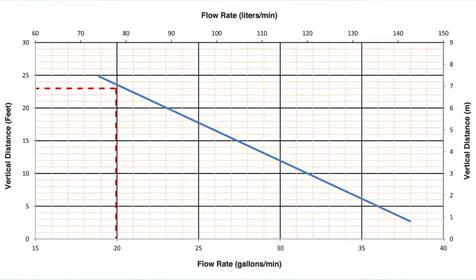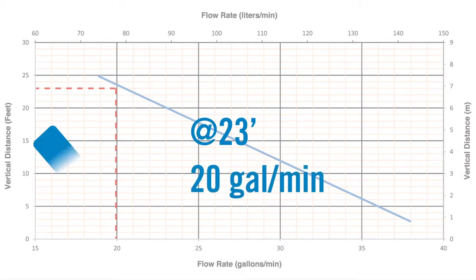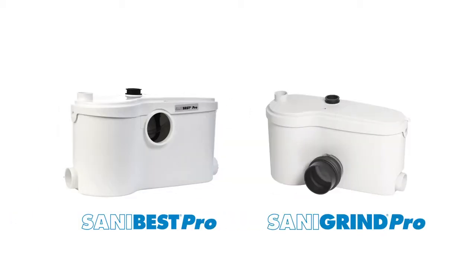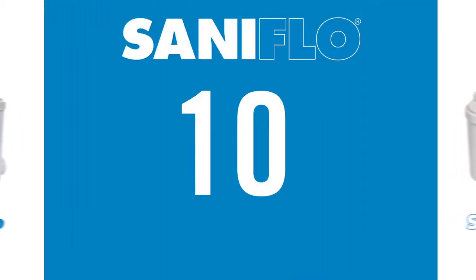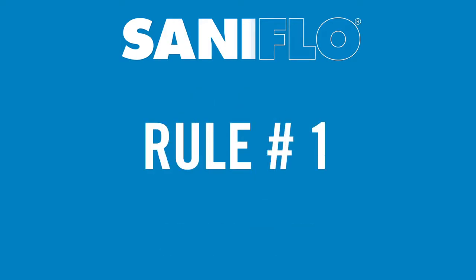By reviewing the pump curve, it shows that at 23 feet, the pump will discharge 20 gallons per minute, which satisfies our requirement. Both the SaniBest Pro and the SaniGrind Pro are perfect systems for this application. Once you've determined the right solution for your job, keep Saniflo's 10 golden rules in mind during installation. Rule number 1.